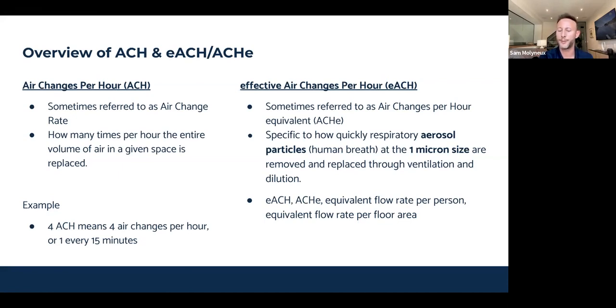All of these, of course, are designed to capture some replenishment and removal rate of the thing we want to remove: respiratory aerosols. Relating this back to what many of us are used to measuring, the volumetric air change rate is calculated in a completely different way. We measure the flow rate at the vents, and divide that total flow rate over the total volume of air in a space, giving us the air changes per hour for a given space.